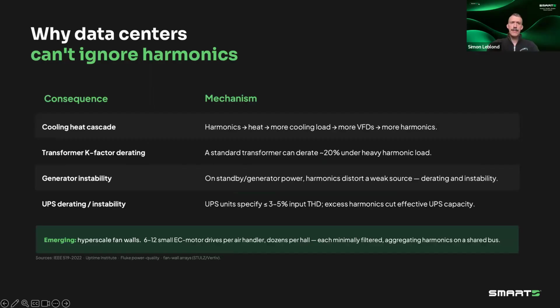If we're talking specifically of data centers and why harmonics are important for data center, we're going to talk about it later, but the number one consequence of harmonics is heat. And so as you have harmonics, you're generating more heat, which requires more cooling, more VFDs, more harmonics. And so you have this kind of heat cascade that you want to manage. After that, and this is true for any facility, a standard transformer derates about 20% under heavy harmonic load. So you're going to have to upsize your transformer, more cost, less efficiency due to harmonics.